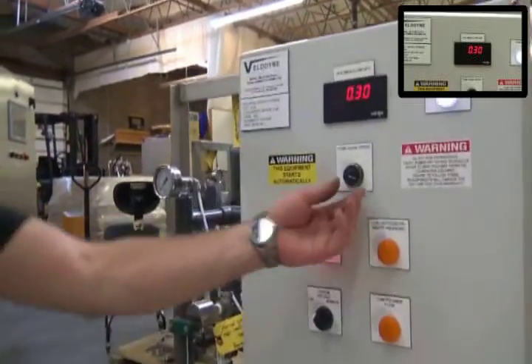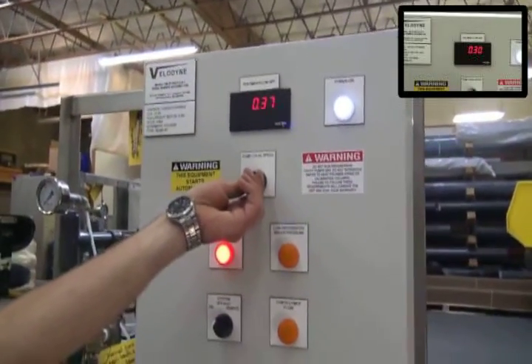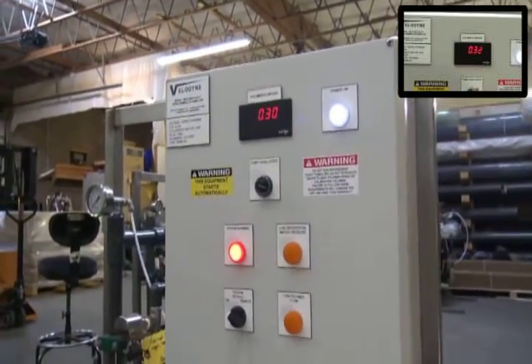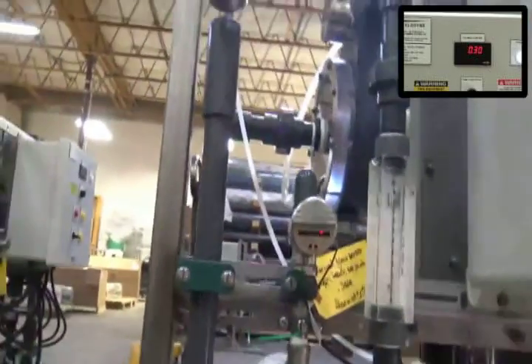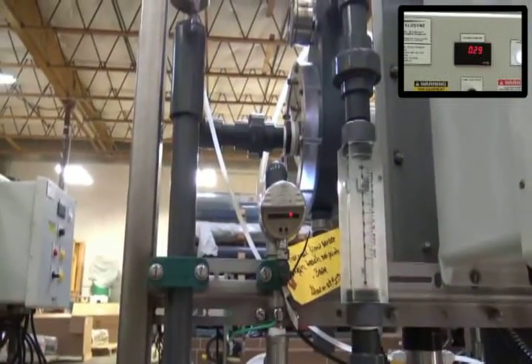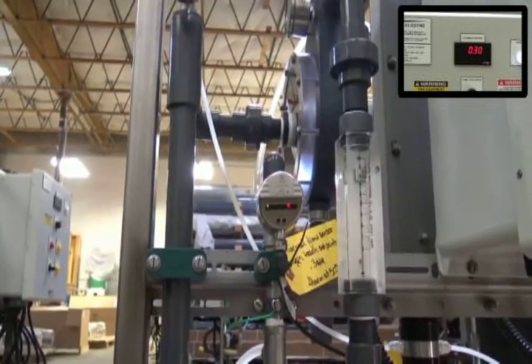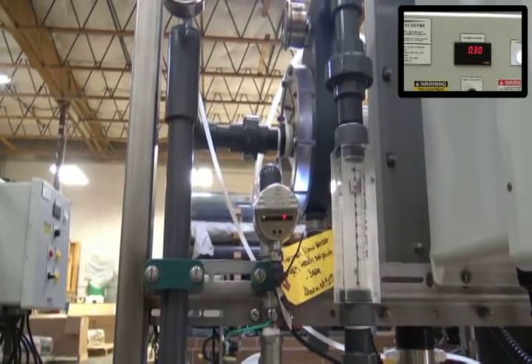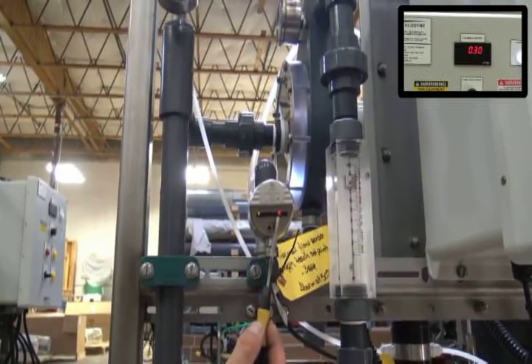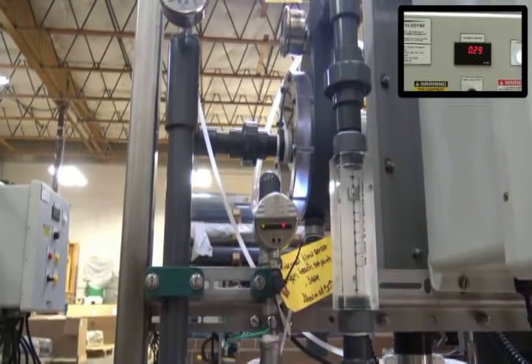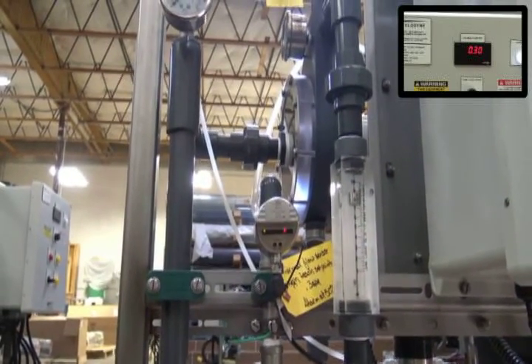By doing that, we just do the local speed control, up and down. And so we got that set at 0.3. Now, come over to the thermal flow sensor. This one has been factory reset, so if you notice the red light on it, that one should be orange right now, so we need to change the state on this thermal flow sensor.